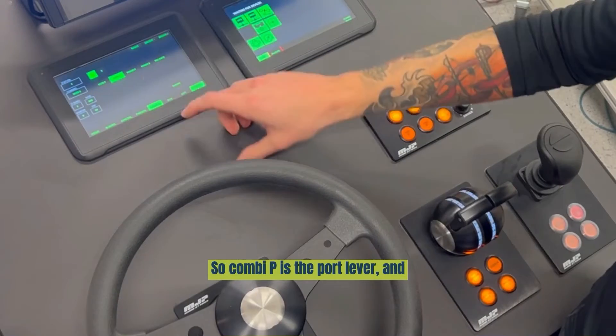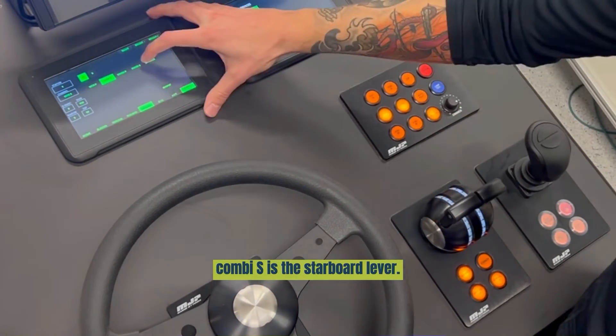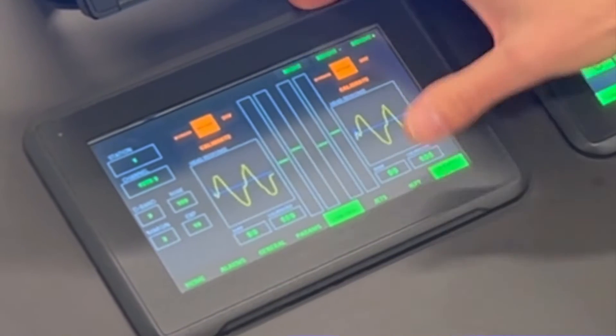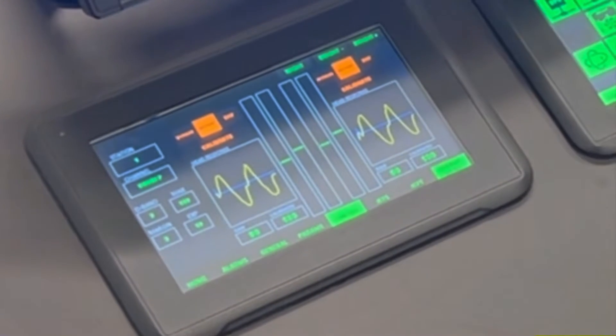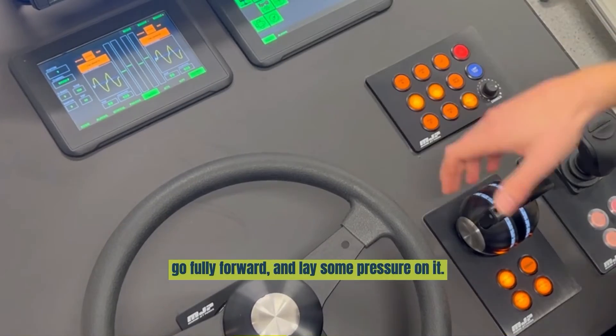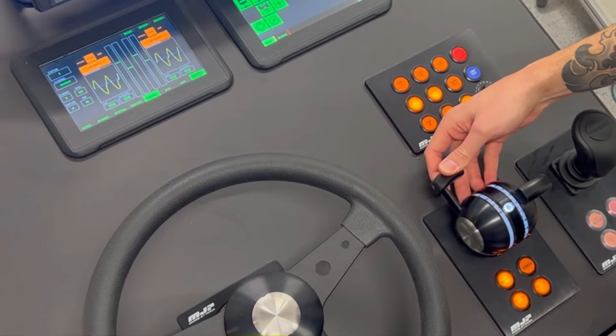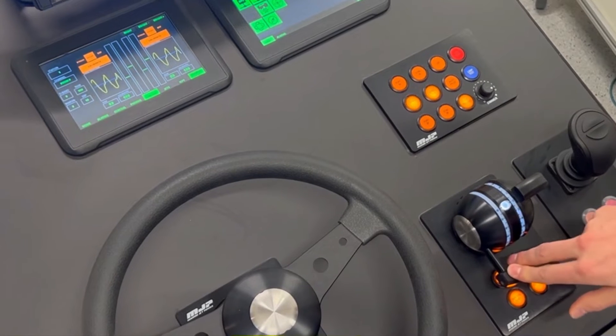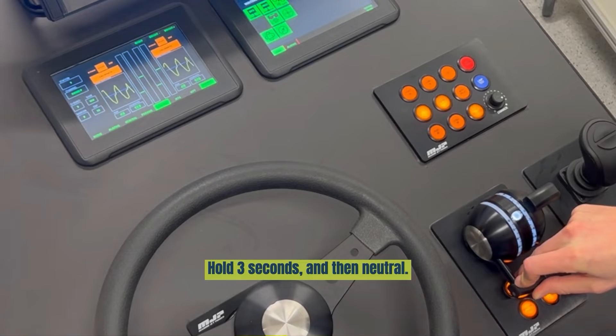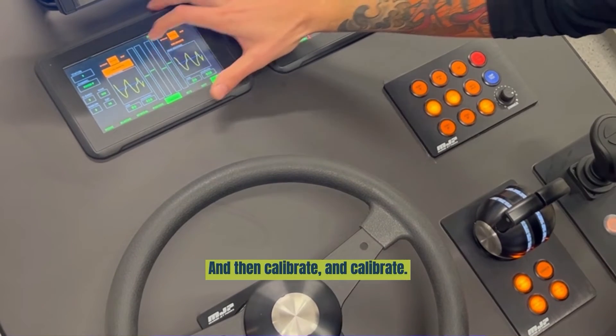Now we can go to the combinator. Combi P is the port lever and combi S is the starboard lever. Start with the combinator port lever. Press calibrate and calibrate. Then go fully forward, lay some pressure on it for 3 seconds. Go fully reverse, lay some pressure on it, and wait 3 seconds. Then neutral, and then calibrate and calibrate.